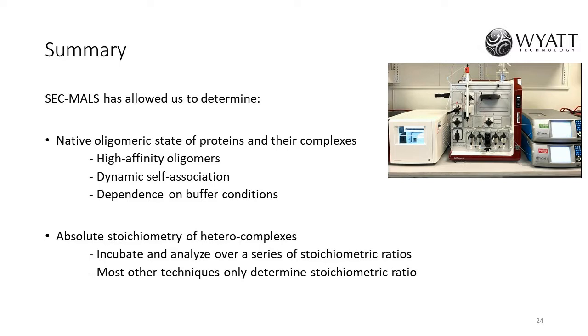What factors should be considered to lower the error percentage with the molecular weight obtained from SecMALS? The easiest way to have good, low errors with your molecular weights is to equilibrate the column and the SecMALS system for a long time — about two hours to sometimes even overnight. The longer the system is equilibrated, the better the baselines are, which reduces the error. Also, a high protein concentration gives much better signal-to-noise.